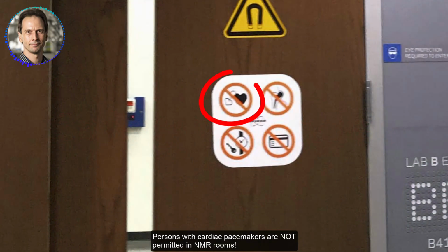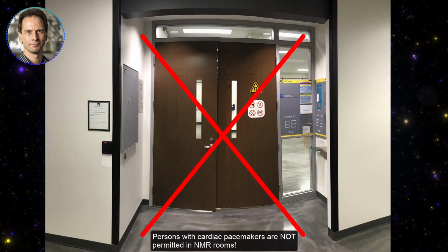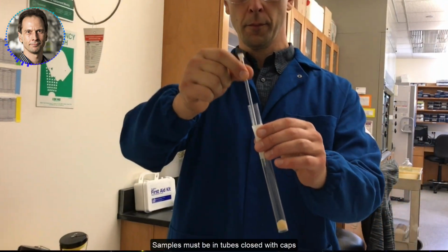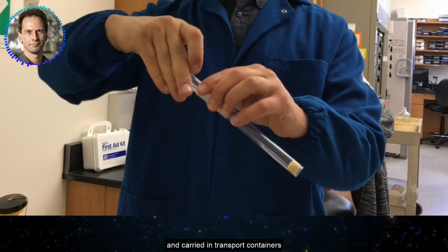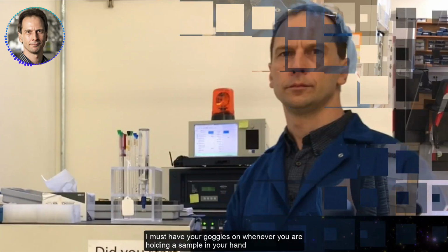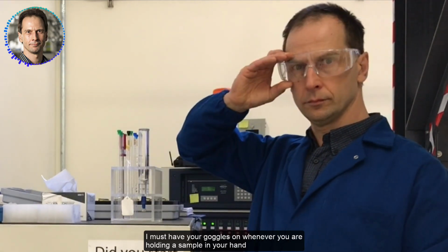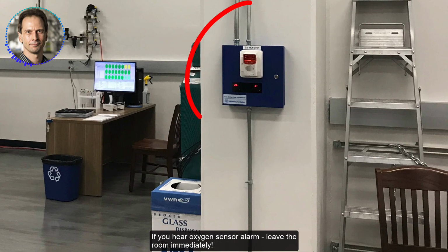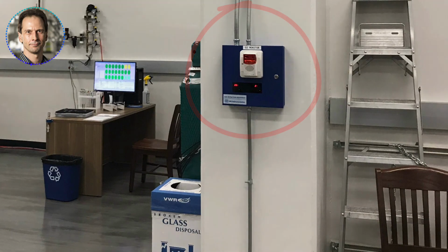Persons with cardiac pacemakers are not permitted in NMR rooms. Samples must be in tubes closed with caps and carried in transport containers. You must have your goggles on whenever you are holding a sample in your hand. If you hear an oxygen sensor alarm, leave the room immediately.